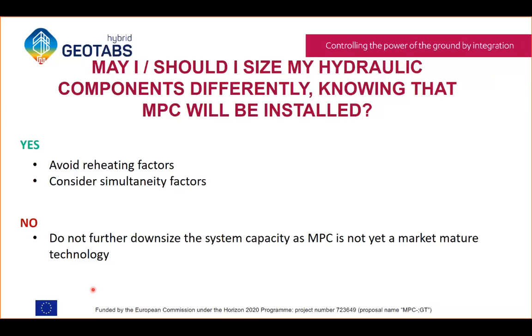But what you should not do is downsize the total system capacity of your building, as MPC is not yet a market mature technology. What I mean is that on the coldest day, -8 degrees, you may still not need so much power if your building was being heated at full power for 3 days in advance. But this is, I think, still too much of a risk to take into account. We first need to see numbers from robust MPC implementations.